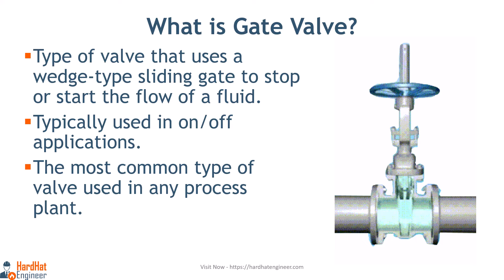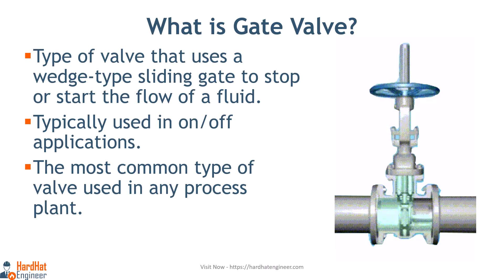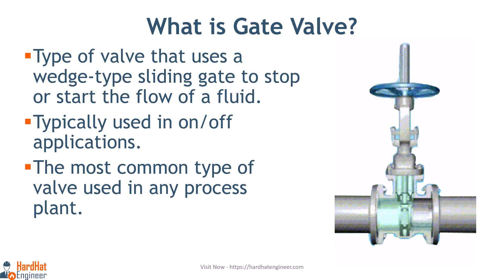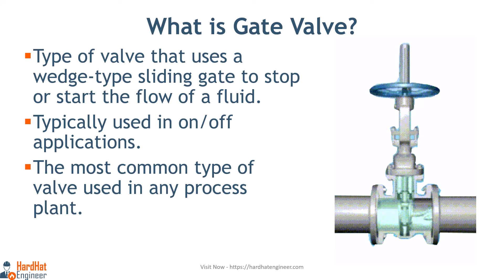It is a linear motion valve used to start or stop fluid flow in service. The valve position is either fully open or fully closed. When the gate valve is fully open, the disc is completely removed from the flow, therefore it virtually has no obstruction to flow, as you can see in the animation. Due to this, very little pressure drops across the valve when fluid passes through it.